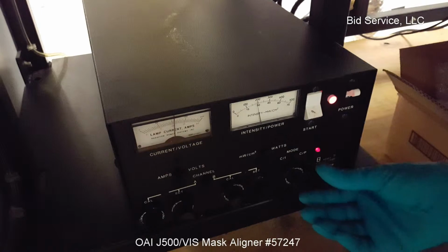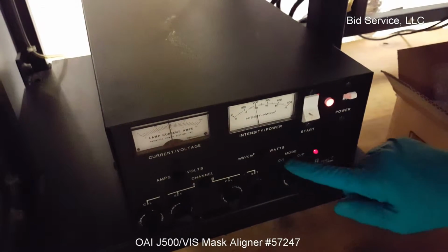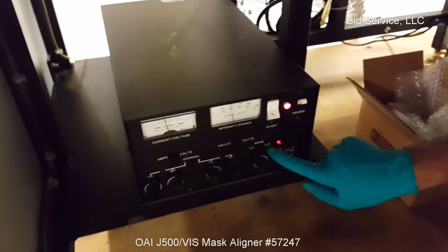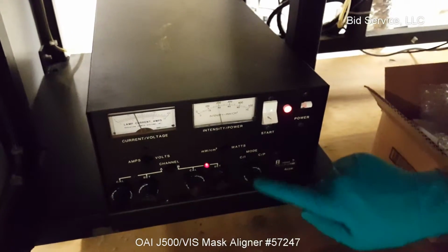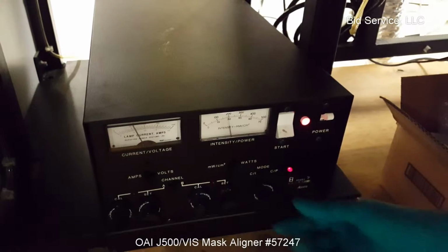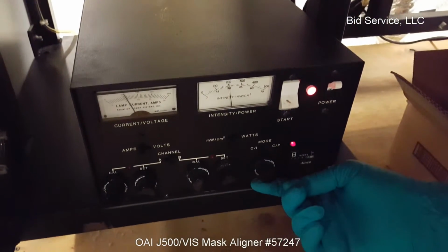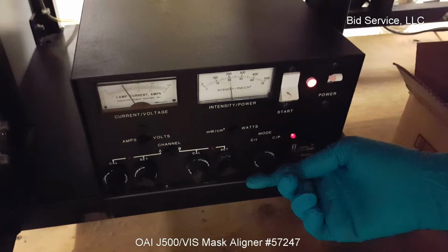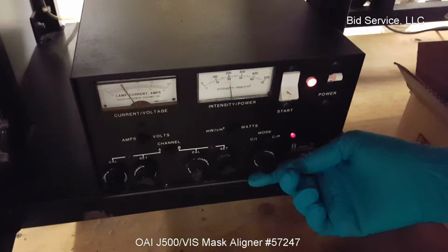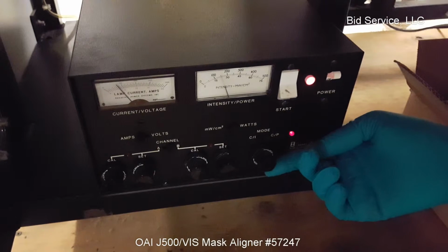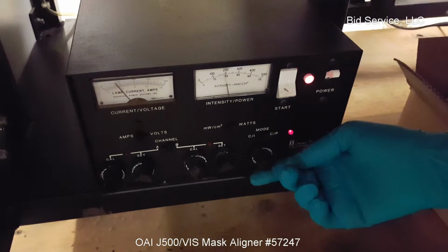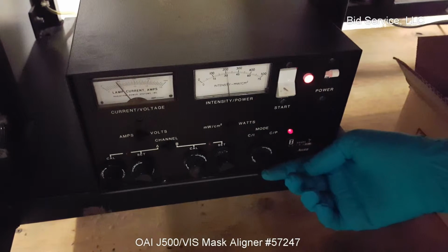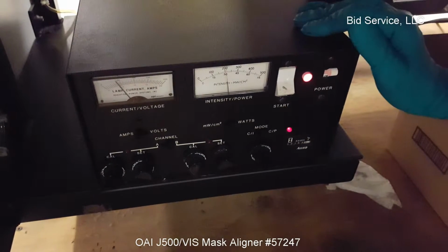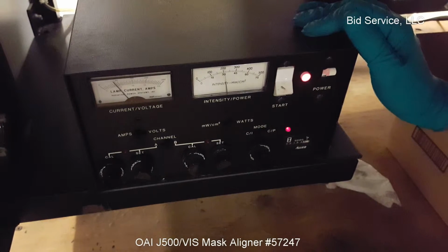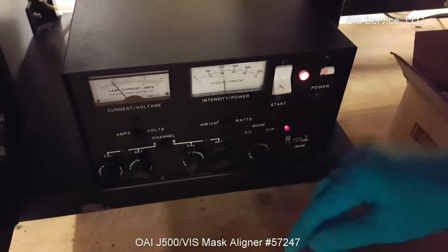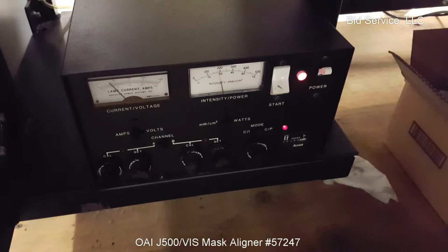It's a 200 watt lamp, and there are different modes of lamp operation: constant power mode and constant intensity mode. When in constant power mode, the knob on the right hand side will allow you to change the power level from 200 watts to 175 watts. The usual idle power is about 170 watts. So when the mask aligner is not in use, but we want the lamp turned on, 170 watts is recommended.